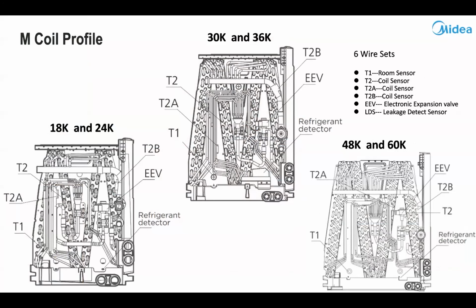So this slide shows you the different layout of different size coils. All the sensors are going to be in a very similar spot, but they will change. They will have minor changes from the 18, 24K to 30, 36K and the 40, 48 and 60. They will be in slightly different spots. The refrigerant sensor will not change. It will be in the same spot every time.